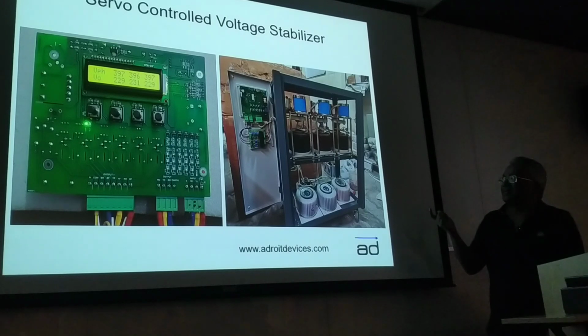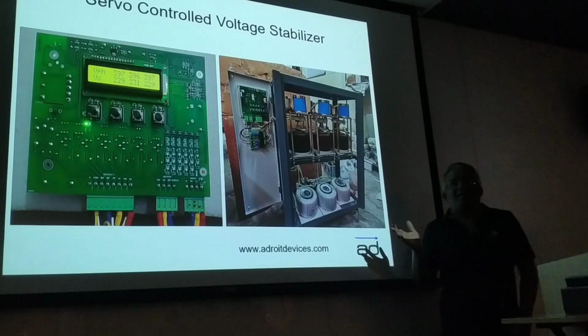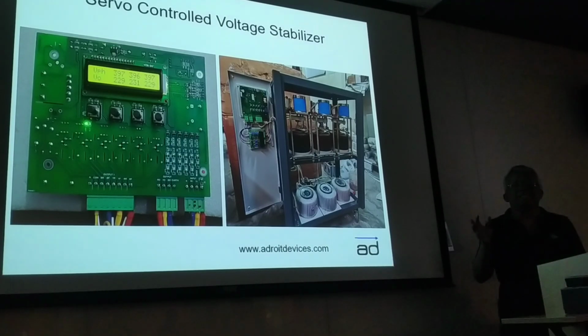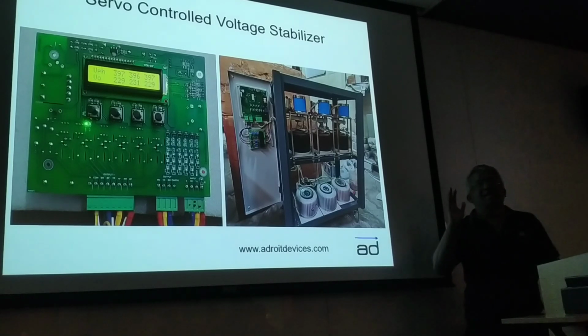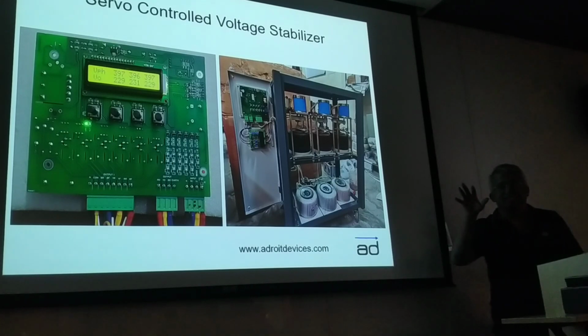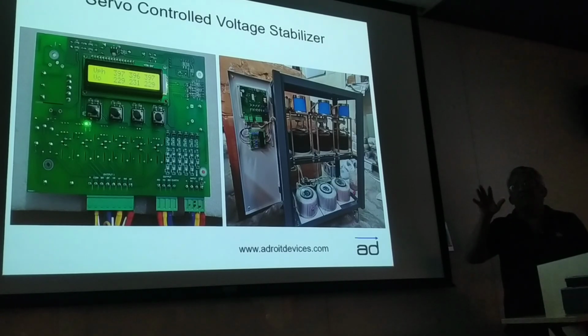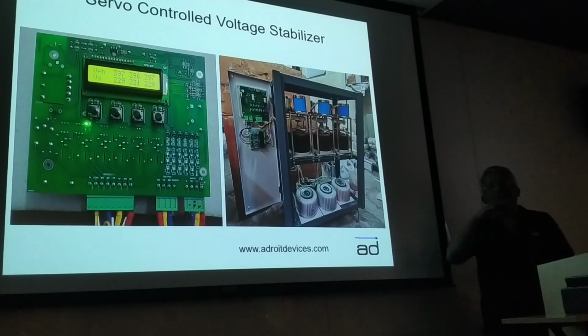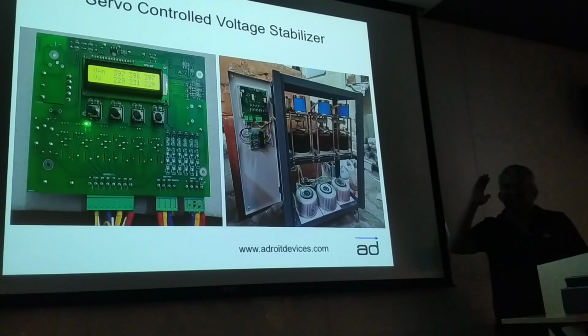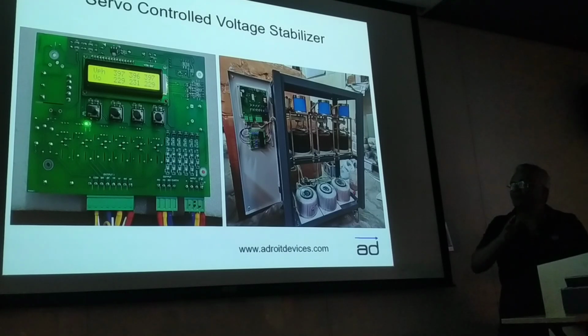So this is actually a servo stabilizer. These are used with CNC machines and such. Wherever there are huge drives, in places on the outskirts of Mumbai where the power is not so good, and most industrial units are generally centered there, in the evening or night when a lot of units shut down, the voltages go high. So if you are running a machine at that time, it's not good for it.